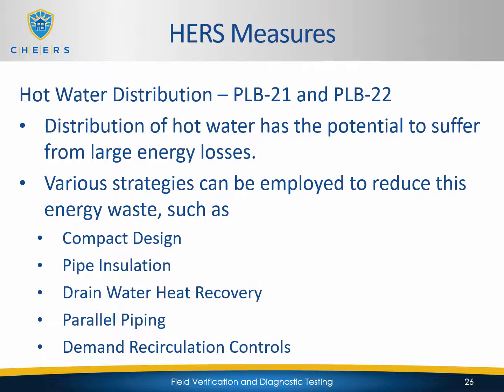There are various strategies that can be employed to reduce this energy waste, such as a compact design, pipe insulation, drain water heat recovery, parallel piping, and demand recirculation controls. So again, just like on the duct systems for the HVAC system, the more hot water lines that you have running, the longer they are, the less they're insulated, the more heat transfer that we're going to have. And it's going to be going from the hot water to the cooler air around it. So we're going to lose that.